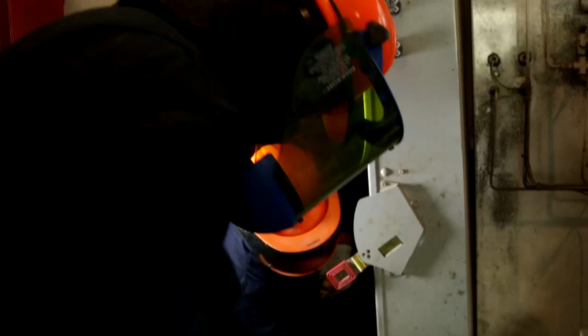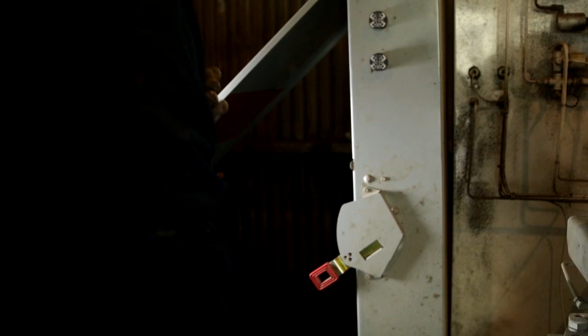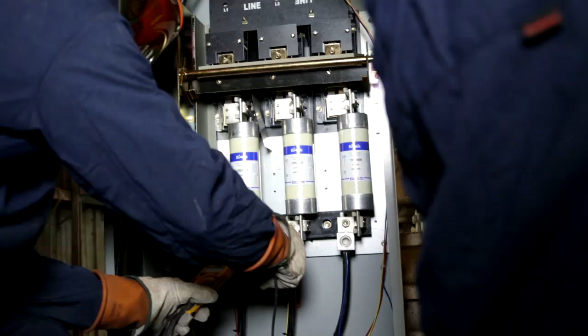When we opened the cabinet door, we found that the voltage indicators were in fact wired correctly, but there was still something wrong. There was no visible indication that anything was wrong until we started to look much closer, and we found that the handle to the disconnect had broken away from the knives because the knives had been welded in place over time. It was eye-opening.